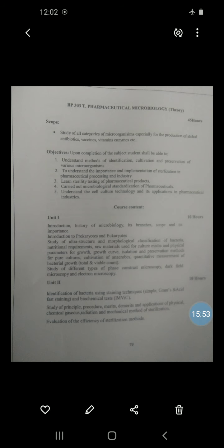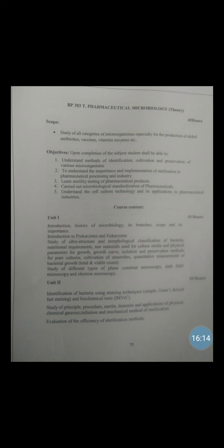The amount and the rate of absorption depend upon the nature, thickness, and surface area of the article, and their wrapping and the size of the load. The amount and the rate of absorption depend upon what? Nature, thickness, surface area of articles, and their wrapping and the size of the load.